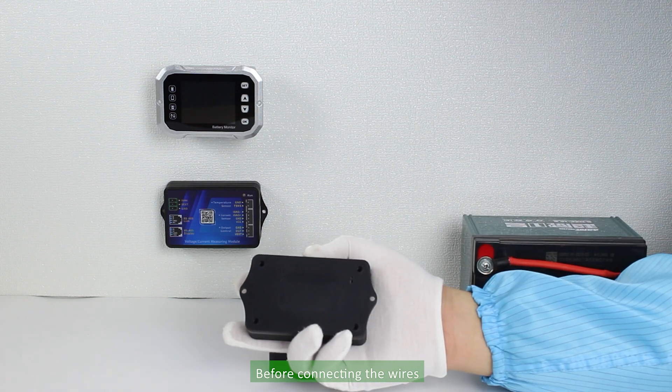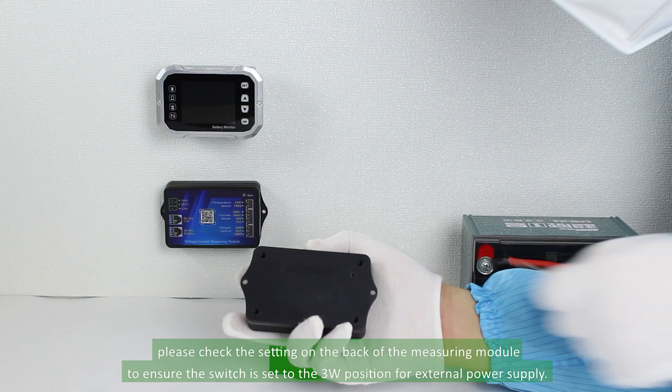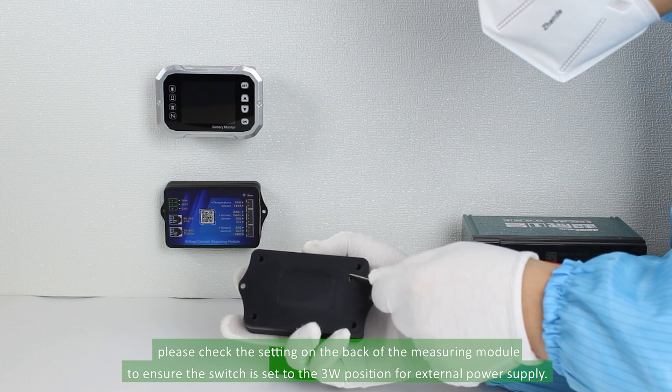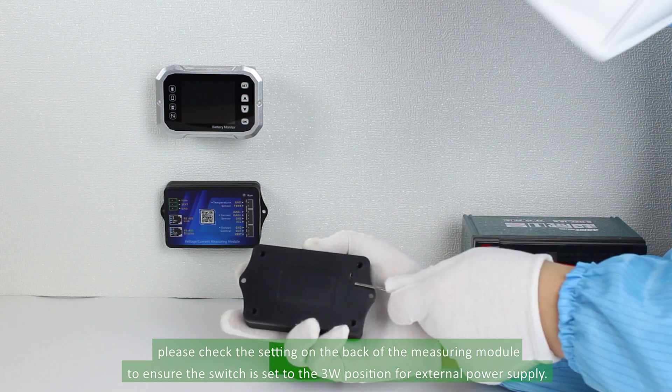Before connecting the wires, please check the setting on the back of the measuring module to ensure the switch is set to the 3W position for external power supply.